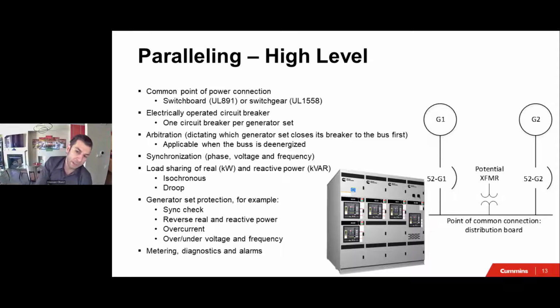We need electrically operated circuit breakers, and we need 1 per generator. We can't get away without an electrically operated circuit breaker. It's for when we're in sync, we want to close, and it also acts as an isolation if we need to disconnect a generator.